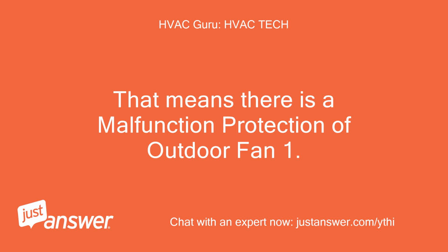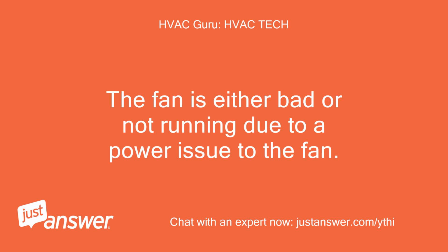That means there is a malfunction protection of outdoor fan 1. The fan is either bad or not running due to a power issue to the fan.